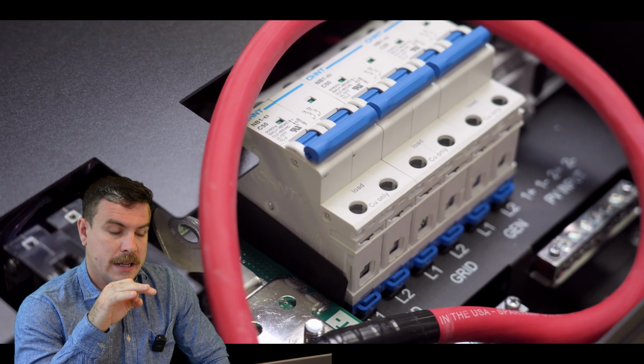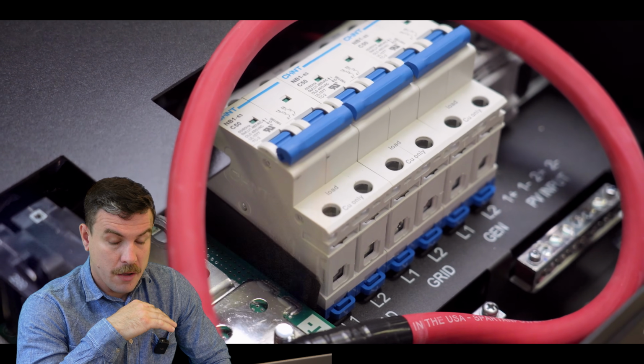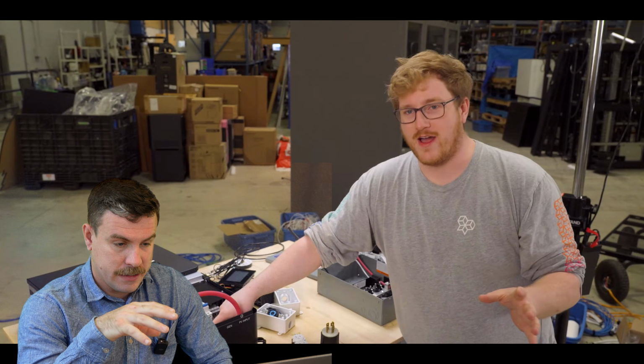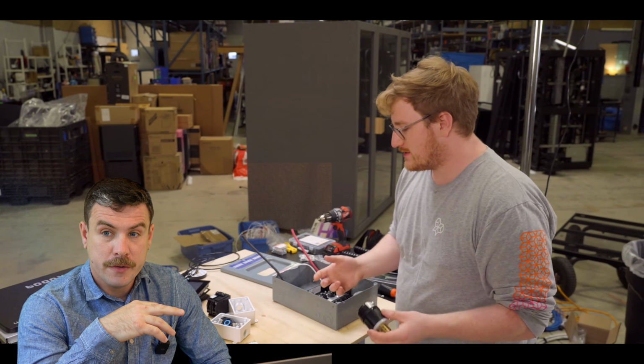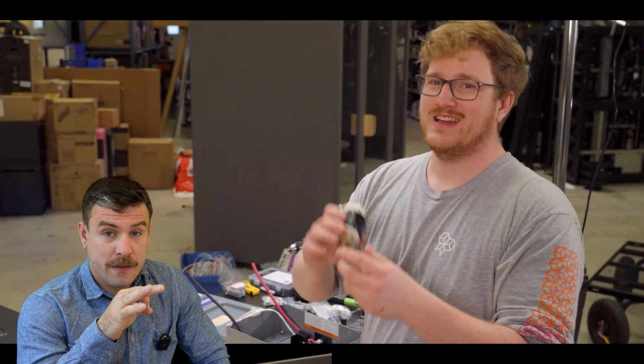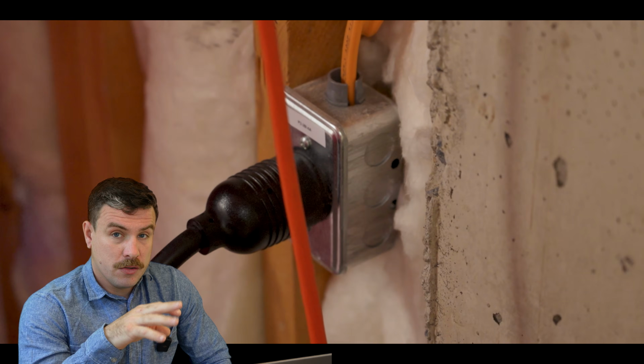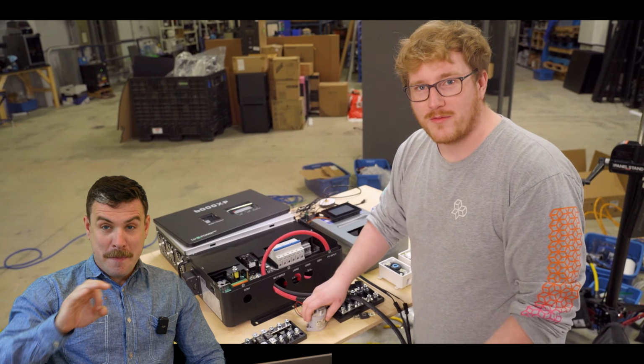Maybe they're relying on disconnecting the BMS and there not being power, but I'd like to see isolators. Now that's another thing with EV packs - they come with contactors on the positive and negative side, and they do insulation resistance tests to make sure there's no power going to ground. So way safer than a contactor just on a bench.